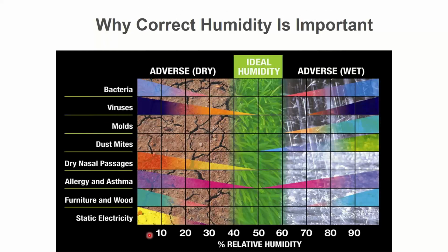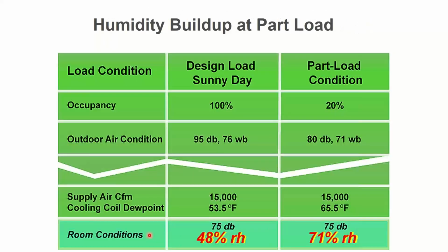Showed you this chart before, although this is a prettier version of the Sterling chart. So humidity control, yes, important. We explained all that. A normal system without an ERV, a normal DX system, I design it for a certain amount of people, for a certain condition outside, right? Some design day, if you will, right? In this example, it ended up being 15,000 CFM I needed. I selected a coil that got me 53-degree dew point, which is awesome, by the way. And I set my thermostat for 75 degrees, and that all ended up yielding me a 48% relative humidity value in the space, which is great.